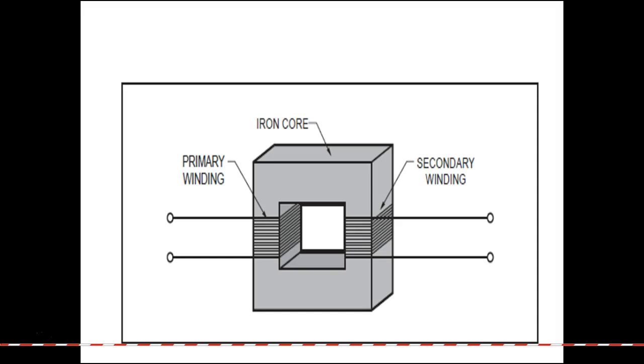What happens when I put the magnetic field in here is it induces a voltage which drives a current, and this would be really big, and it would get hot, and the transformer would be very inefficient. So what we do is break this core up into hundreds of individual little plates and insulate them from each other. We call those laminations.